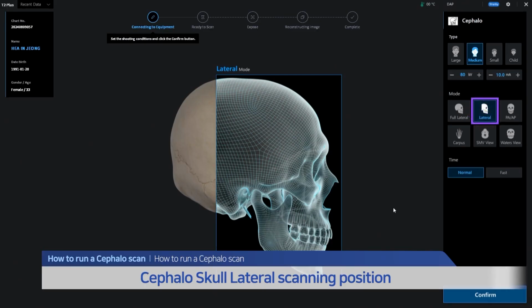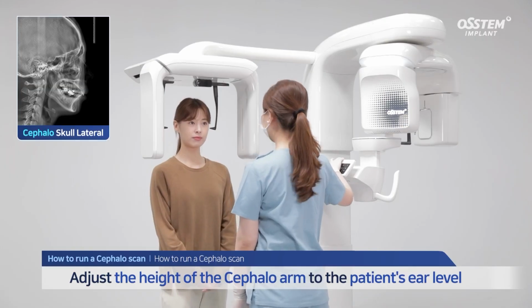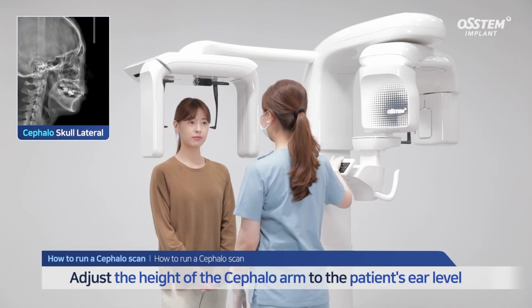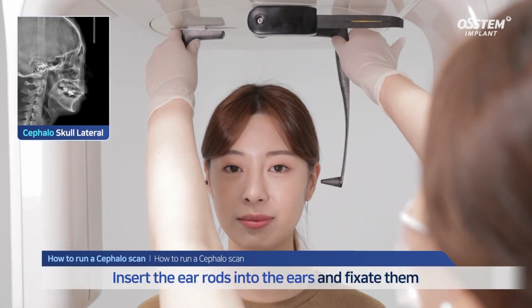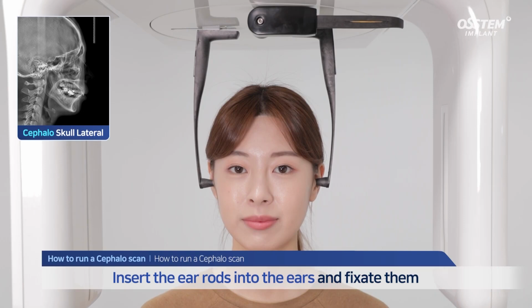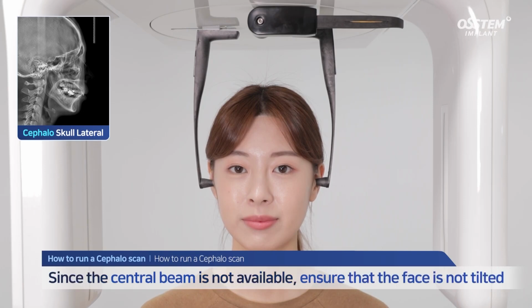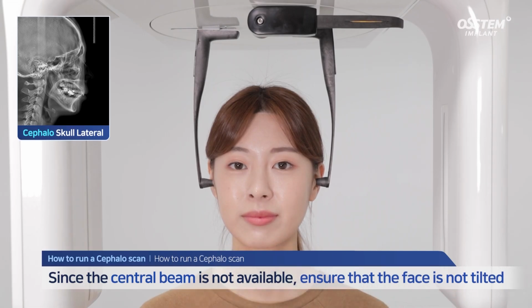Let's take a look at the cephalo skull lateral scanning position. Adjust the height of the cephalo arm to the patient's ear level. Insert both of the ear rods into the patient's ears and fixate them. As the central beam is not available, make sure that the face is not tilted sideways.